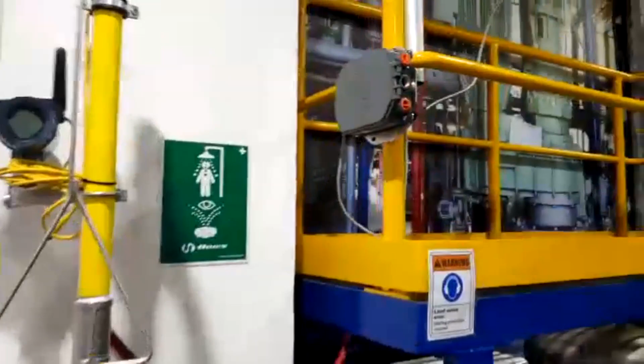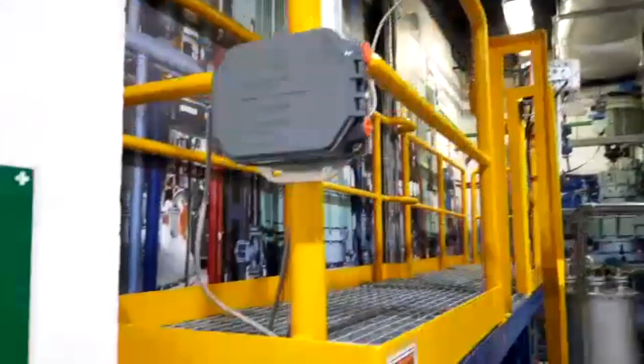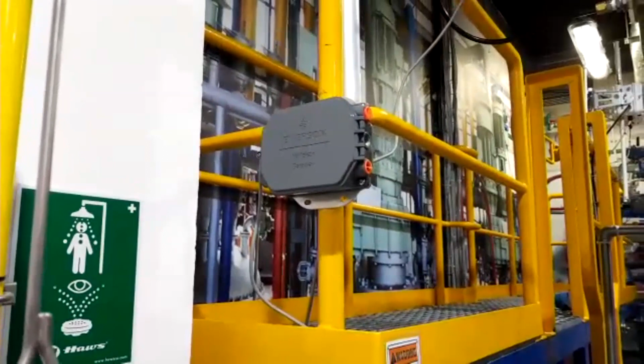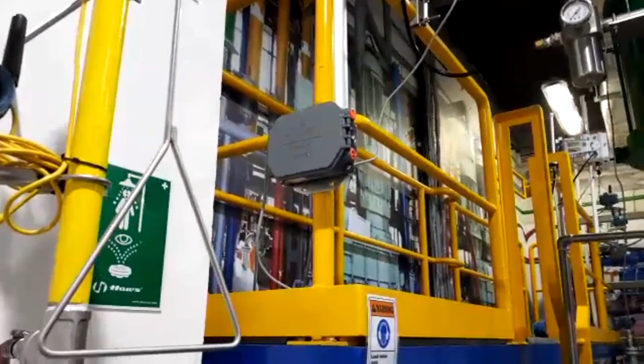So this is the wireless HART gateway, and up there you can also see the radio. This wireless HART gateway also supports automatic conversion to HART-IP, OPC UA, and Modbus. That makes it very easy to integrate the data into data lakes, historians, your DCS or PLC, dashboards or analytics, and so on. Other wireless technologies do not automatically convert data to other protocols this way.